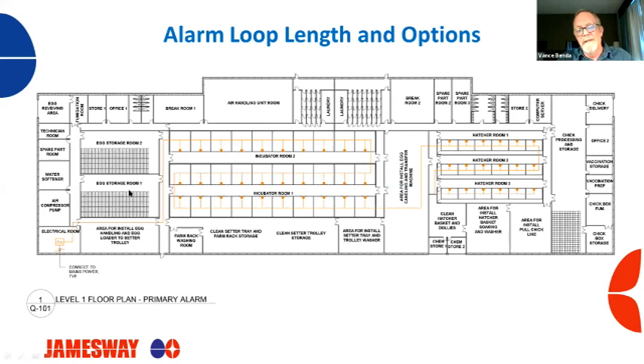And if you were running this system, you're just going to have one horn. And when it goes off, all you're going to know is that either an incubator or a hatcher is alarming. You don't know which one. So we could do a couple of other things. We could mount one alarm box here, one alarm box here, and connect those to horns that make different sounds. So you have one sound for your incubators, one sound for your hatchers, and that's also going to cut down on the length of your loops, because if you had your box here, your loop is going to go through, back up and through, and would stop right here. Same with your hatcher. If your box was mounted here, your loop would stop over here. Much shorter loop and two different sounds, one for incubator, one for hatcher.